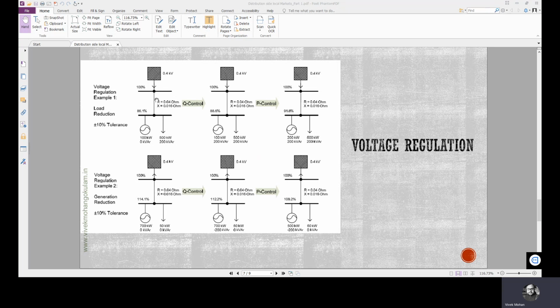Now, because of this current flow in the line and the drops, the corresponding voltage drops, the voltage profile at the local node is 86.1%. Now we are trying to control the reactive power from the local generation side by increasing the local reactive power generation from 0 kVAR to 200 kVAR. Now the voltage profile has improved from 86.1% to 88.6%.